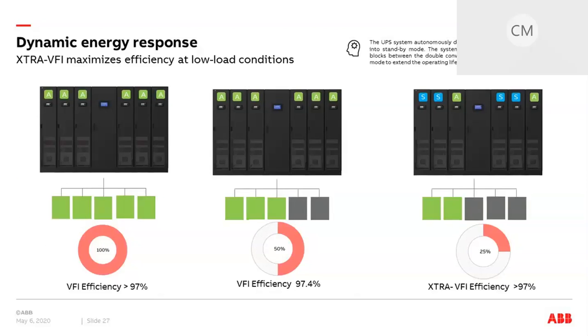In case cloud providers have the ability to balance the capacity amongst the locations due to the different time zones, then the load is reduced to less than 30%, and the UPS system decides which UPS modules go into standby mode, reducing the energy consumption and sharing the load with the remaining power modules. In this case, the efficiency of the system is improved. But how much is this impact? Let us review the following example.